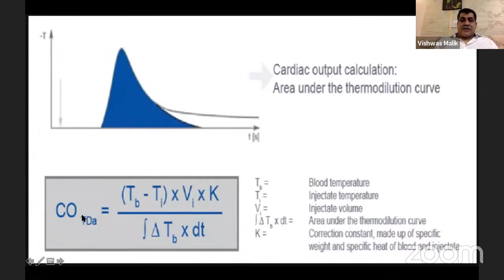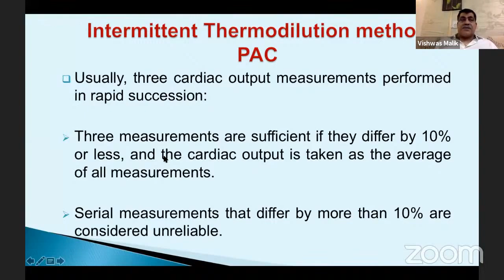Usually 3 cardiac output measurements are performed in rapid succession. If the difference in the measurements is less than 10%, then the cardiac output values will be reliable. If it is more than 10%, this means the cardiac output measurements are not reliable. So it is important to know the values in each part. We have to take 3 values, and the difference in the 3 values should not be more than 10%.